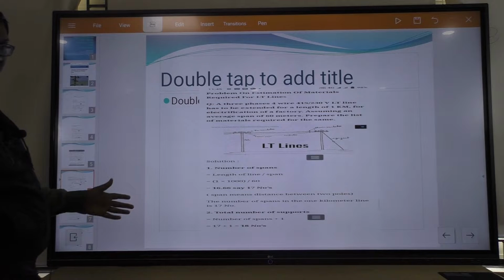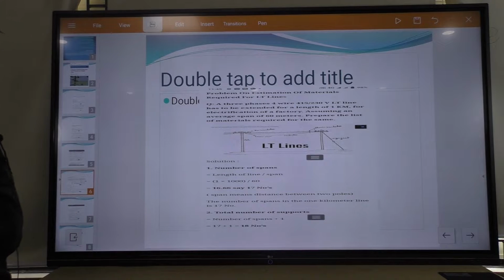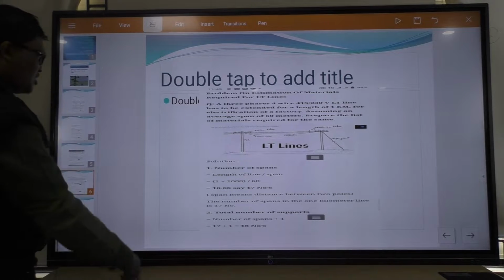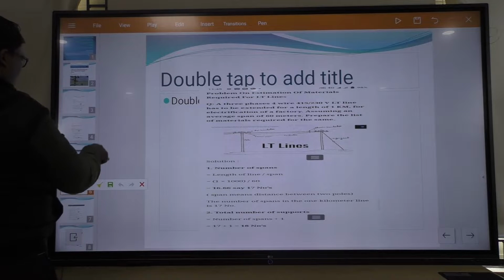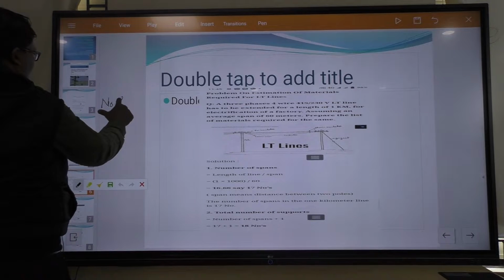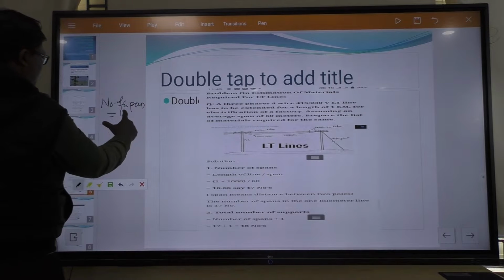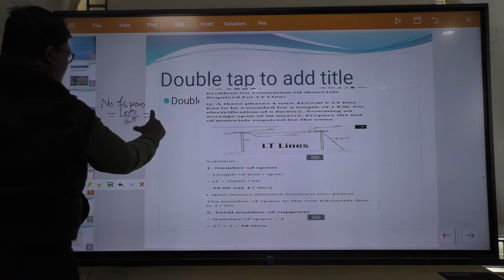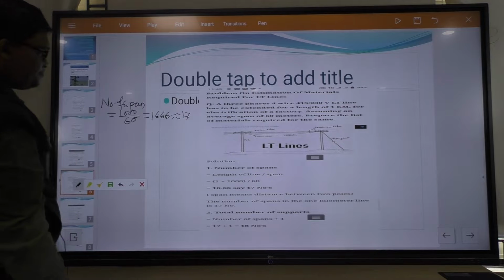LT line. So what we have discussed in the theory, the length here is 1000 meter, and the span is 60. So the number of spans will be 1000 by 60, which comes to 16.66. So you will take it as 17.